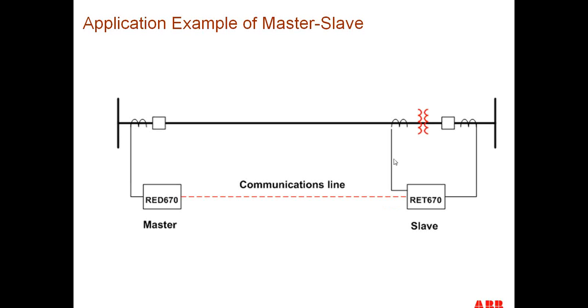There's a case where we have a transformer terminated line, as we showed before. In this case, we have an RET670, which happens to be a transformer differential relay doing its normal protection around the transformer. But in this particular case, we put an LDCM module, our communications module, in the RET670. So we're taking the information from the high side of the transformer and feeding that information to the remote end of the line, where we have an RED670 relay. The RED670 is a line current differential relay. It does the calculations about whether there's a fault on this line section, and if it determines there's a fault, it sends a transfer trip back to this RET670 to trip the low side breaker. So this is an example of how you can use a master-slave arrangement where you don't have two of the same relays on each end of the line.